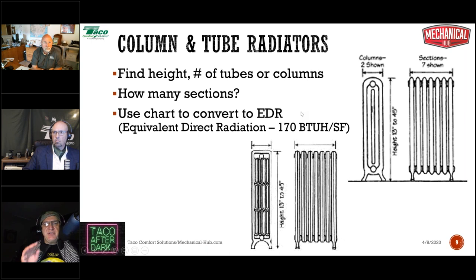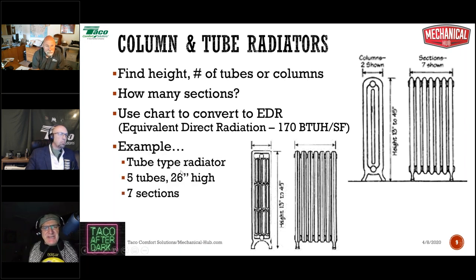All right, and then you use a chart, which we're going to show you next, to convert to EDR, or equivalent direct radiation. And equivalent direct radiation is like 170 BTUs per square foot at a certain water temperature, which we will show you. All right, so let's do an example.